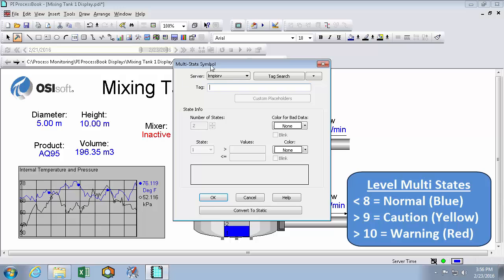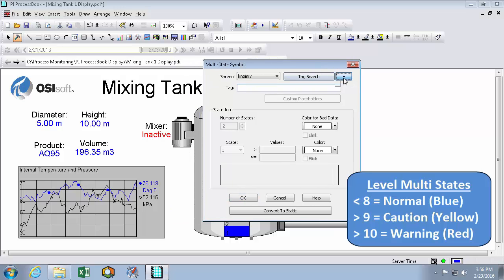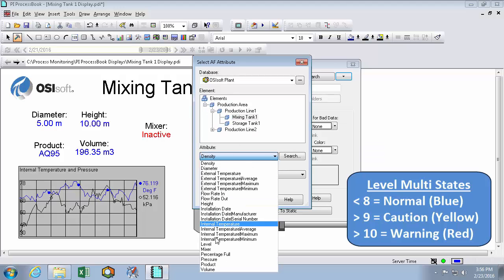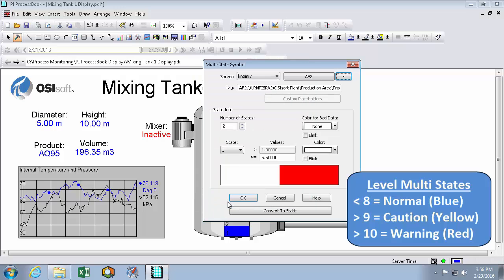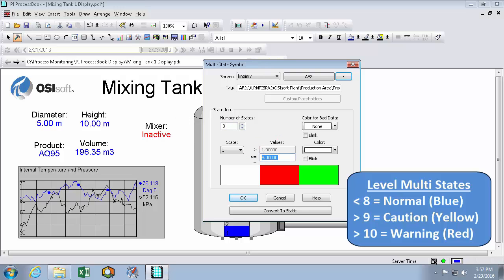So editing the multi-state. This time we'll use the attribute level. And we're going to bump the states up to three states. So now we have to choose the boundaries of our states. And we can see here that the lower level is bound at 1 because it's gray and I can't change it. That's because the PI point is configured to only have values between 1 and 10. So the first state, like I said, will be between 1 and 8 and will remain blue.